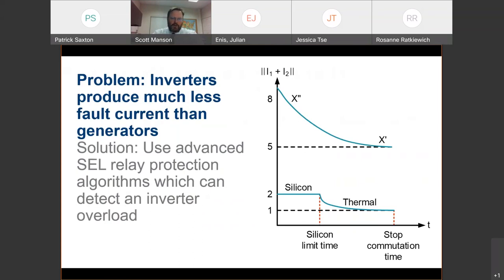Here you see it, that for a short period of time, limited by what we call a silicon time limit, the silicon can only handle so much current for a period of time, at which point the controls, it's a hard limit. After that silicon time limit, they back off and they pull back to a thermal limit. Remember, as an inverter operates, current passes through those conductors and through that silicon, and that creates heat. That heat has to go somewhere.